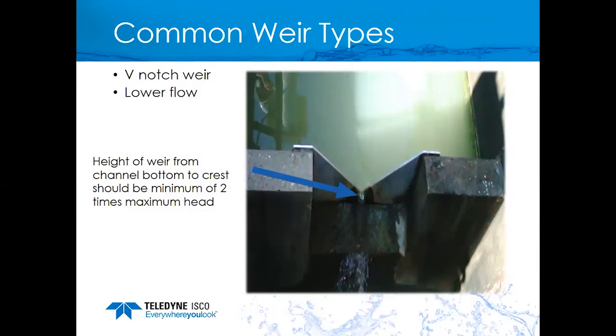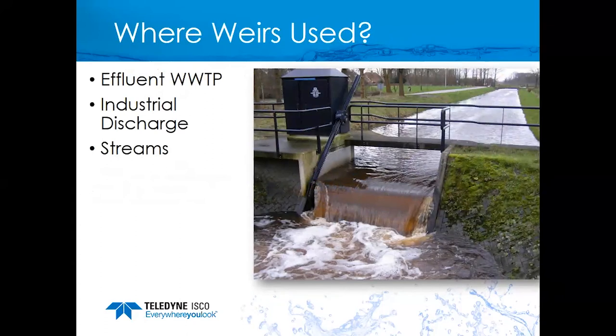Another common type is the V-notch weir, used in lower flow applications. The size of the weir depends on the expected flow rate through the channel. The height of the weir from the channel bottom to the crest should be at least two times the maximum head to determine weir size. The ISCO Flow Data Handbook has excellent sizing examples — consult the ISCO website to get a copy. Weirs are commonly used at the effluent of wastewater treatment plants where solids have been removed, and also for industrial discharge and streams.